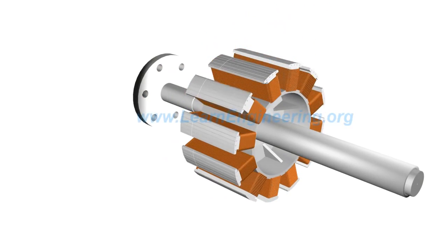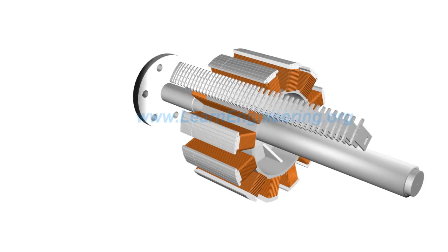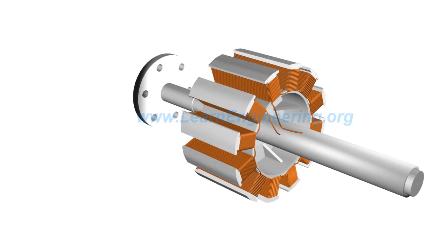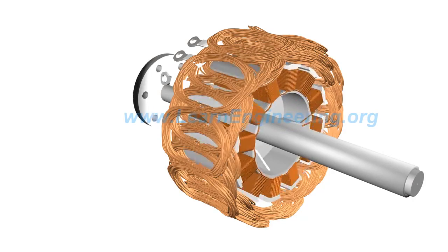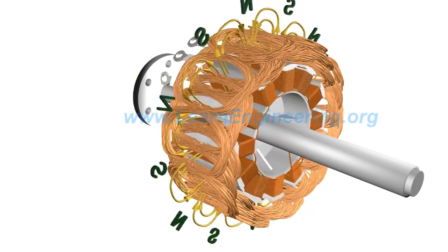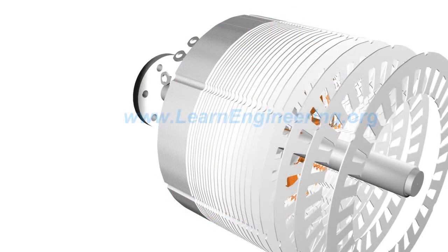Pole core is used to effectively transfer magnetic flux, and is made with fairly thick steel lamina. Such insulated lamina reduces energy loss due to eddy current formation. Armature winding of a 3-phase, 12-pole system is shown here. A stator core is used to enhance magnetic flux transfer.